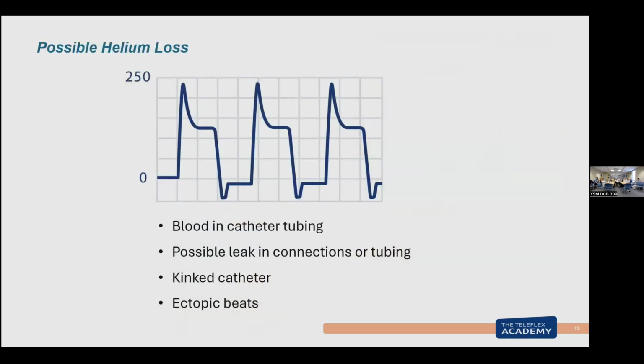So that's looking at that. Now, we have two levels of possible helium loss alarms. It'll say possible helium loss, there'll be a 2 behind it, or possible helium loss 3. It's looking at this waveform and looking at the baseline. If it drops down below 0 and doesn't get back, I'm going to get a possible helium loss alarm. Two levels. These are the basic things that we look at.